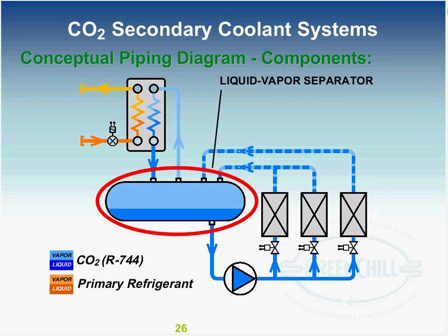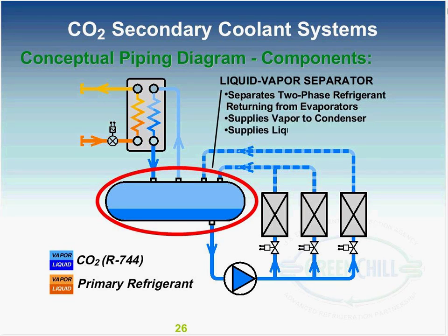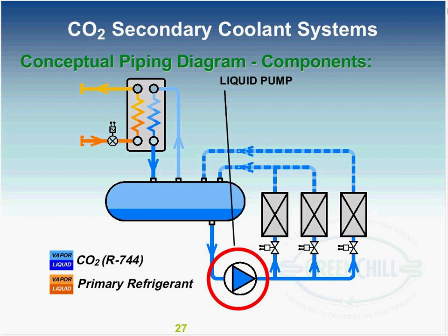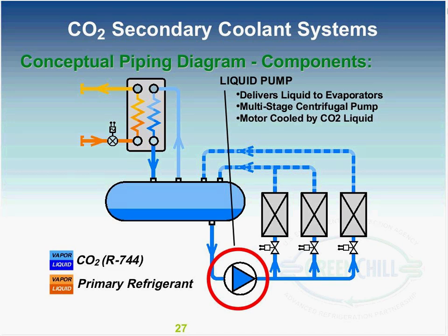The next component is the separator, and the job of this pressure vessel is to separate the vapor CO2 returning from the sales floor and let it rise to the top and recondense in the condenser again. The liquid falls to the bottom and is pumped out into the store. And then the liquid pump. Now this pump is much smaller than the picture that Bruce just talked about on a glycol system. It's a multi-stage centrifugal pump. This is the only special component for CO2. All other components are standard HFC refrigerant, standard off-the-shelf components, with the exception of this pump, made primarily to pump liquid CO2.